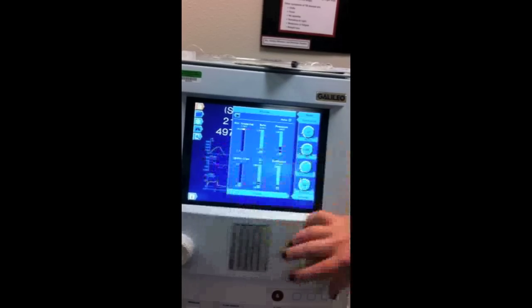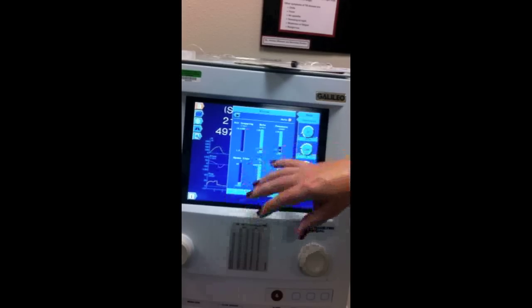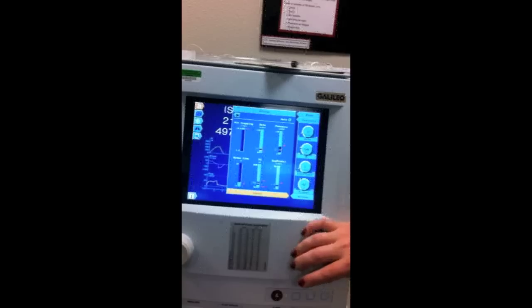So now we're at air trapping, which we don't use. You could actually set it to watch for air trapping. Auto, if you wanted to have the ventilator just pick the alarms, it will automatically default to these here, and then you can go in and change them.